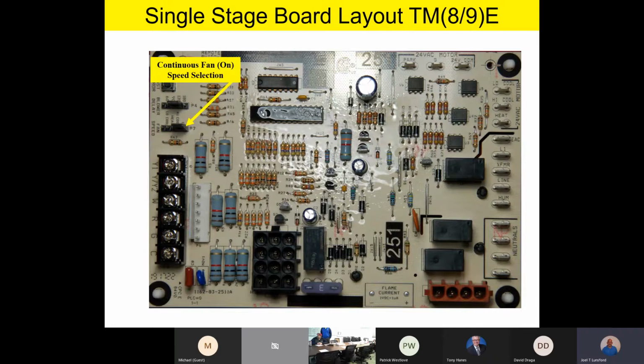Okay, as we move around the board again, as we look at the board straight on, right above our 24-volt terminals, there's going to be a jumper selection called fan speed. This is a pretty cool feature about our Champion TME board: it gives you some options for continuous fan. Instead of some of our competitors, where if you get a fan-only call and the homeowner goes over to the thermostat sub-base assembly and selects fan auto to on, the fan just runs at either 50% or typically 100% airflow, this jumper gives us some options. If you want the fan to run at something other than 50% or 100% airflow, this jumper allows you to select at what speed the fan is going to run on a continuous on fan call.